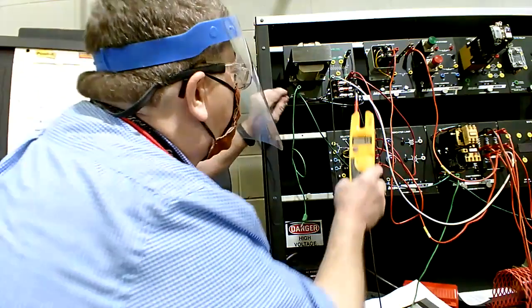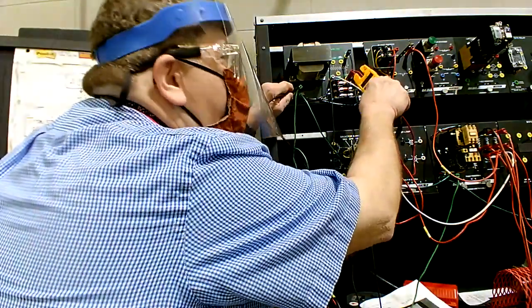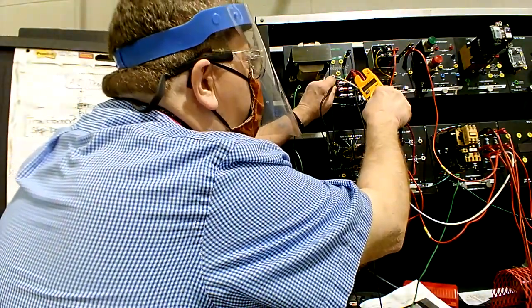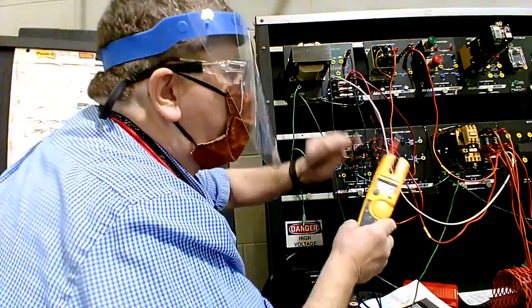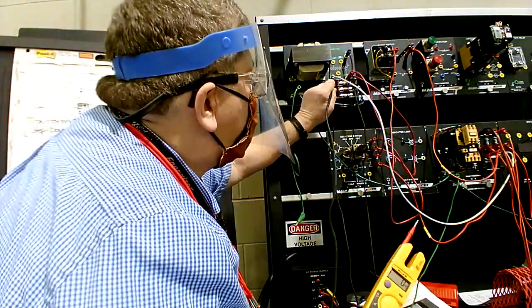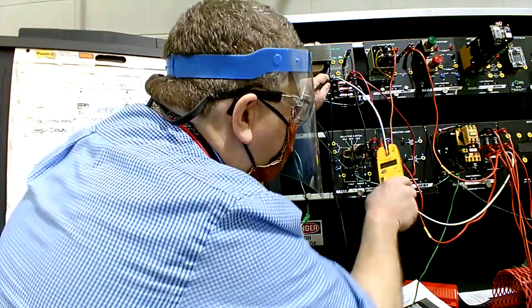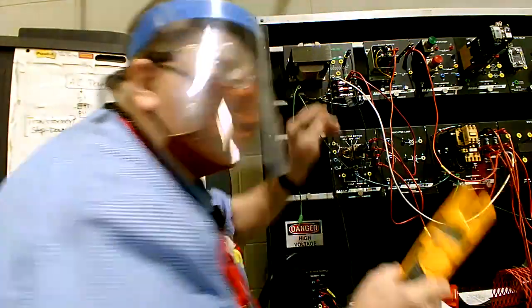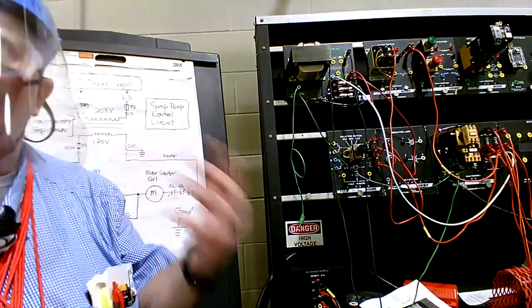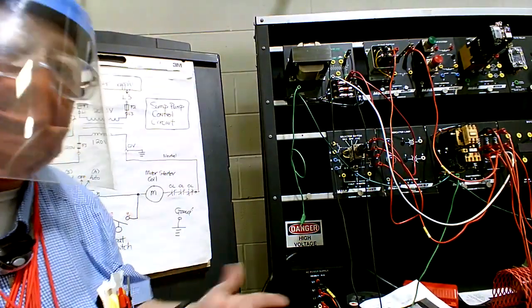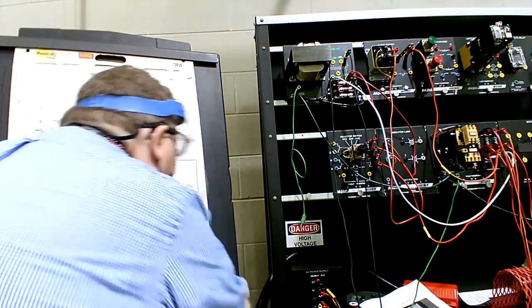Okay, so when I go from ground to here, it will be a bad number, but if I go from neutral to there, it'll be a true number. So therefore, I got to put one lead of the meter on real neutral to check my signals as they go through the circuit. Now let's just demonstrate that, and it won't take you but just a second to see it, and you'll know that this is the issue between floating and grounded. Okay, so we're going to cut it on.